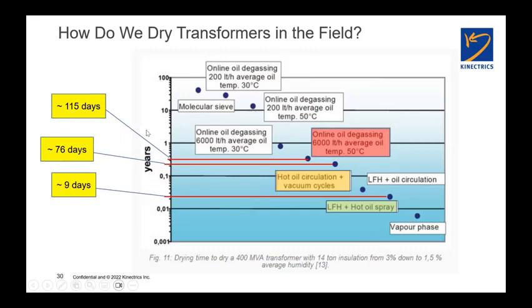And at this point, if I ever have folks that I'm talking to that are on the maintenance side that do this kind of work, they'll say, well, that's crazy. Nobody leaves an oil processor connected to a transformer for 115 days, or 76 days for that matter. And you're absolutely right. And you're not drying the paper and the insulation, you're only drying the oil.